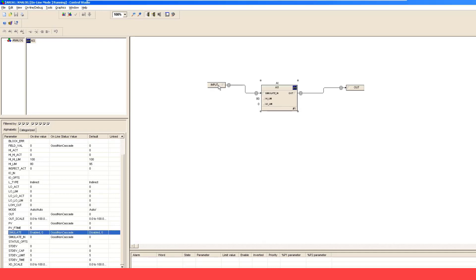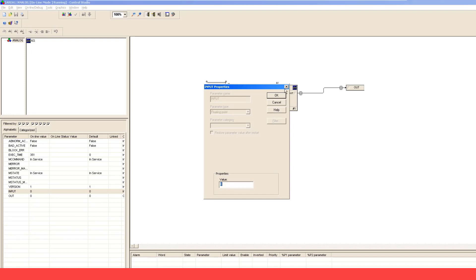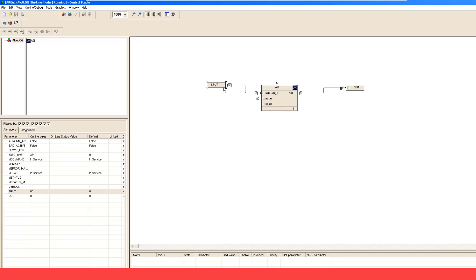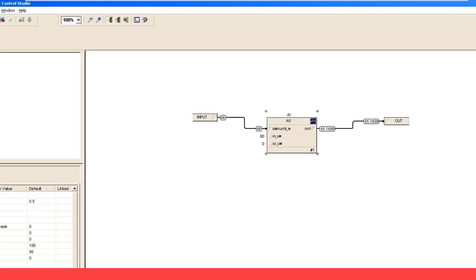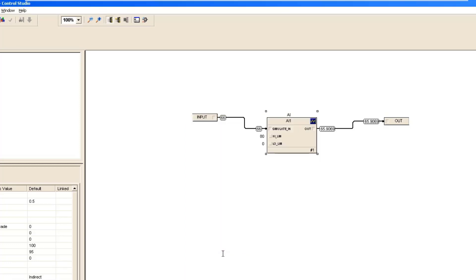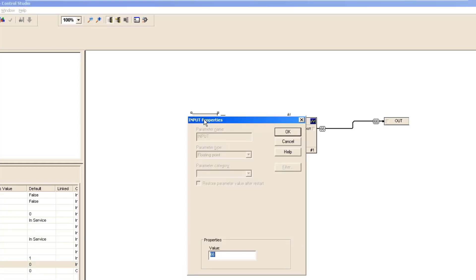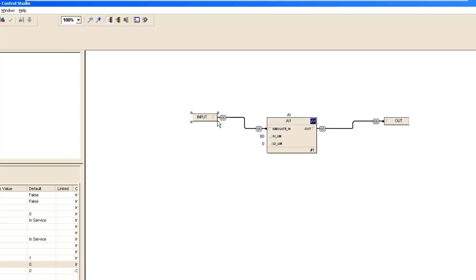After this you can apply any input and see how it works. For instance, if I apply 66, you see that the value 66 is already here and it's slowly transmitting to your output — it will get to 66 because we have applied a PVF time. If you set the PVF time to 0 and change the value — for instance 44 — you will see the effect is immediate: it changes to 44 immediately.